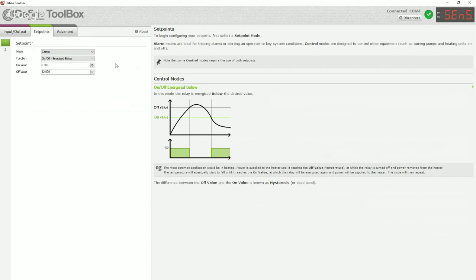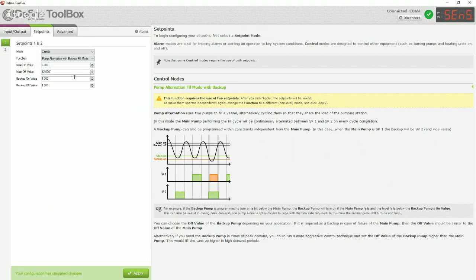You can see here on the right a diagram of how that mode works. Let's have a look at the pump alternation mode, because this is a really neat one that I'd like to show you, because it's quite powerful for this application. So we're going to look at the pump alternation with backup in a fill mode. So that's a lot to get your head around to start with, but basically what we're going to do in this is we're going to use the two pumps. So we're assuming that the tank has got two pumps, so that the load is shared between them, and if one of the pumps fails, the other one will take over. That's what the backup part of that mode does.